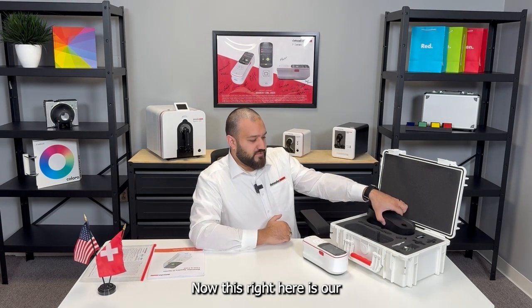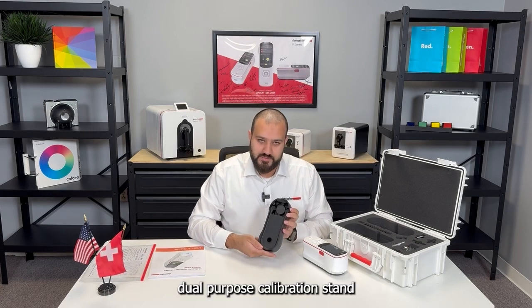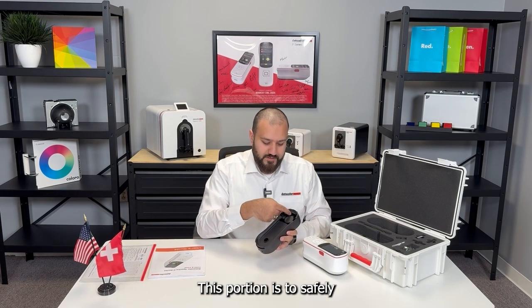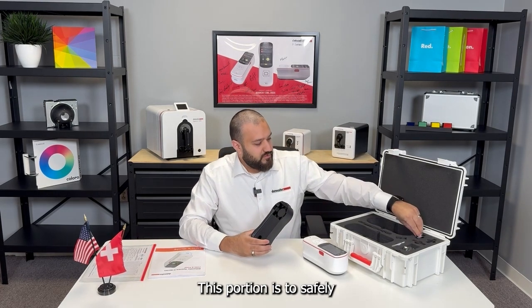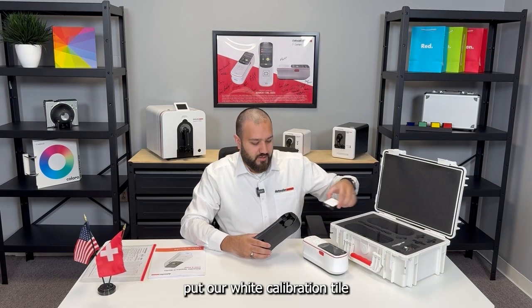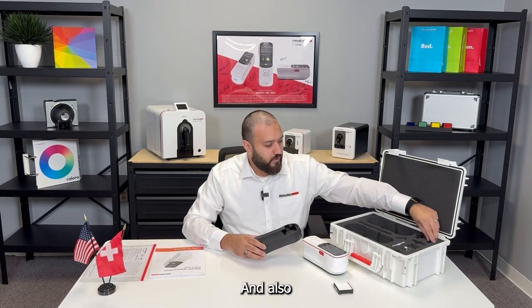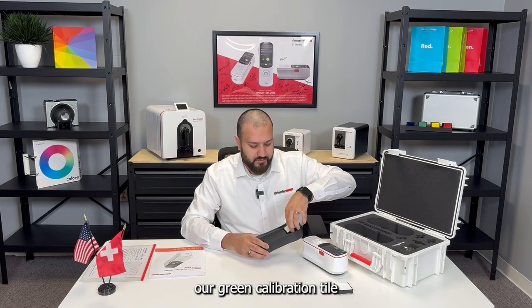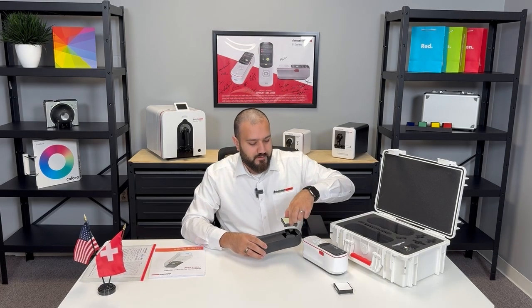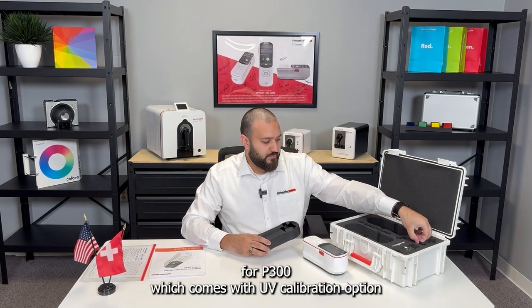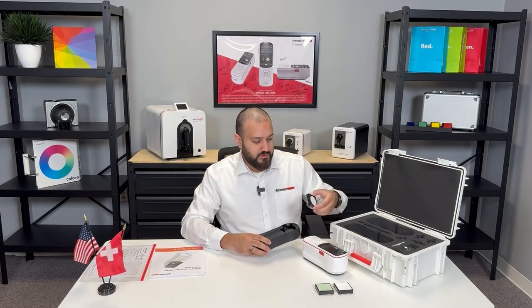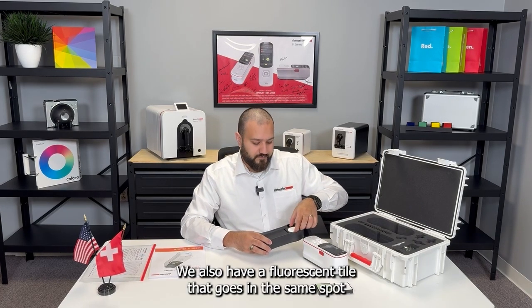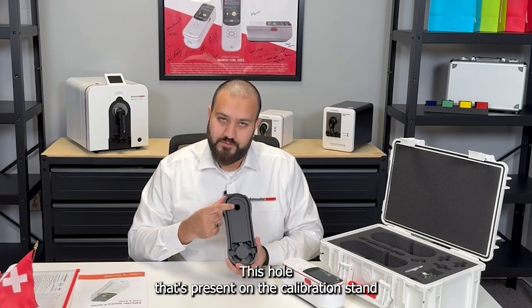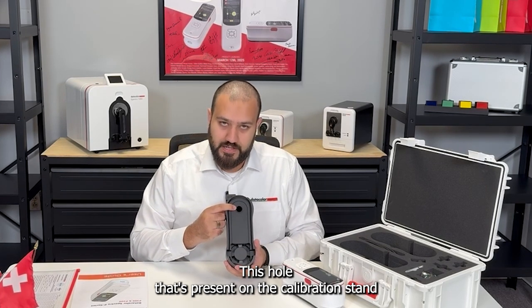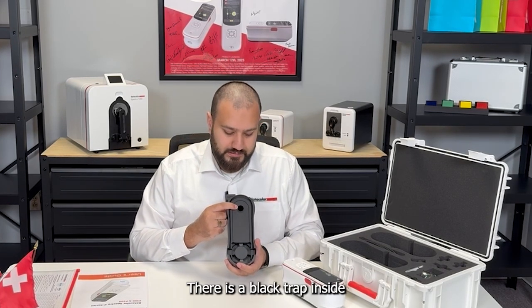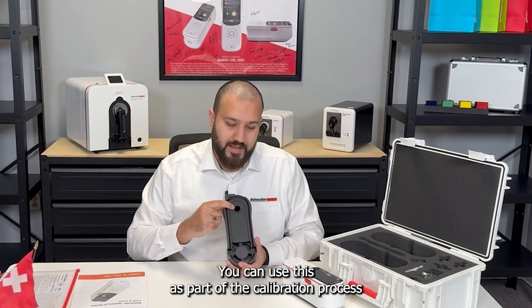Now this right here is our dual purpose calibration stand. This portion is to safely put our white calibration tile and also our green calibration tile. For P300, which comes with UV calibration option, we also have a fluorescent tile that goes in the same spot. This hole that's present on the calibration stand, there is a black trap inside. You can use this as part of the calibration process.